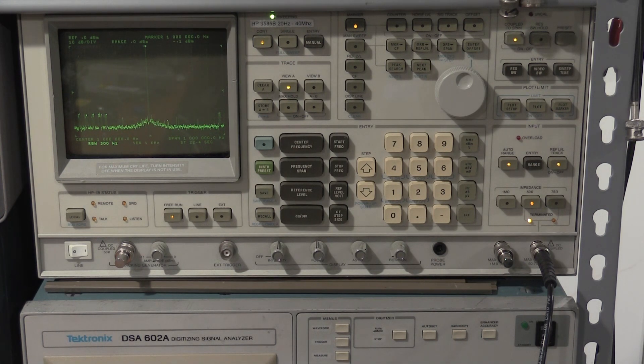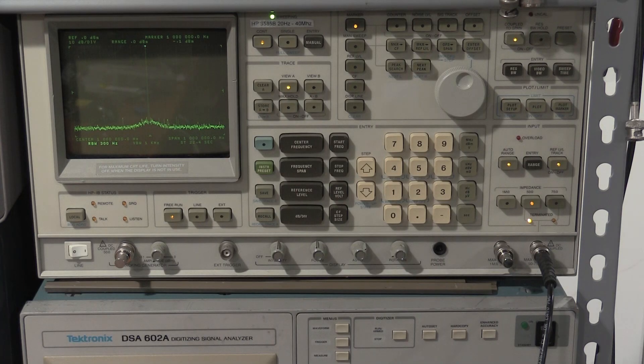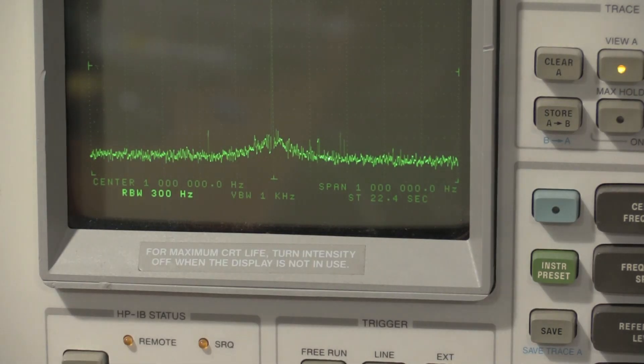Well, it's changed. So I'm still getting weird spikes on the noise floor with the power meter unplugged. Now that coincides to the there are two additional modules that go with this setup that are looking for the monitoring computer. Let me unplug them. But given that this changed, we're on the right track. Well, that's looking a lot better. So if we take a look at our non-harmonically related noise, we would be negative 82 dBm down from the carrier.